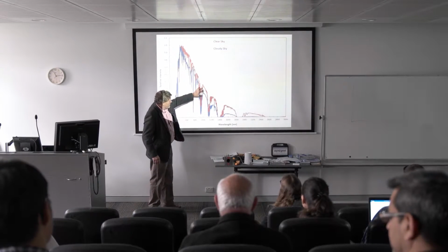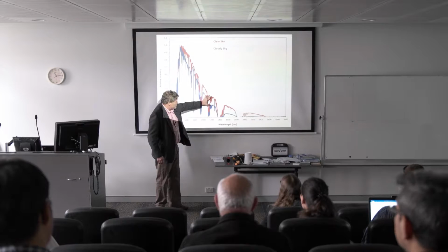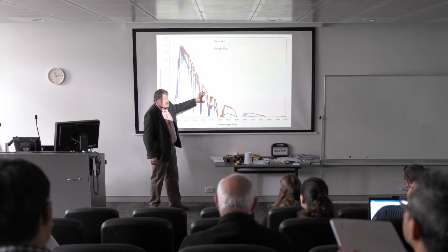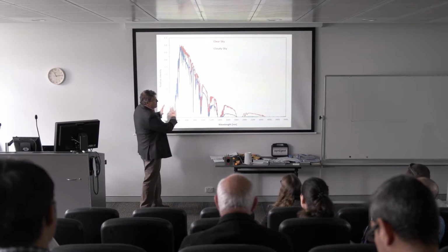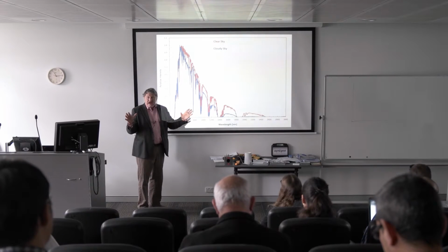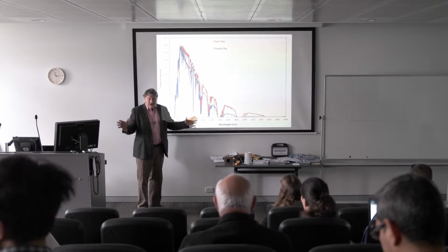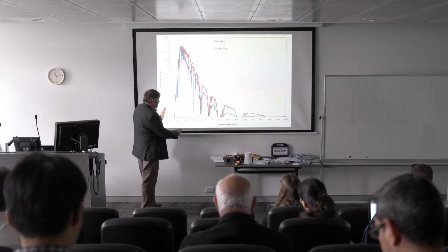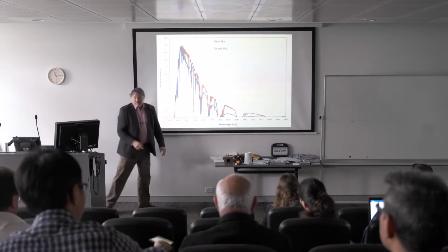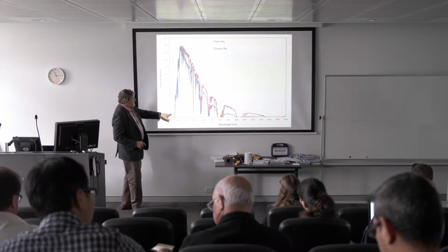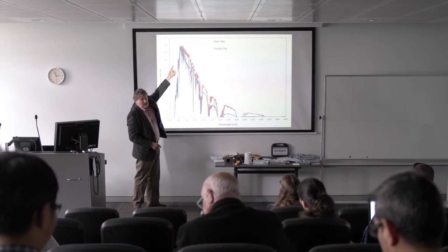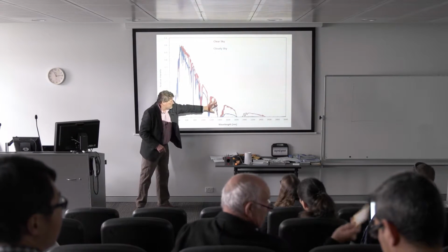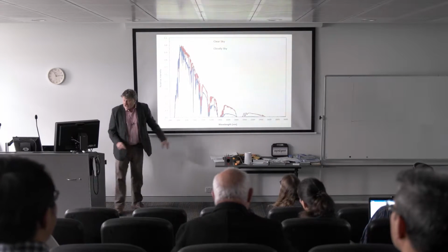Atmospheric water vapor not only takes out these bands, but it greatly reduces these bands of radiation. If you measure the whole thing with the black body pyranometer, you accurately measure this. But if you're only subsampling it, look at this. This spectra is hardly changed in the short wavelengths on a cloudy day. It selectively shifts the wavelengths this direction.